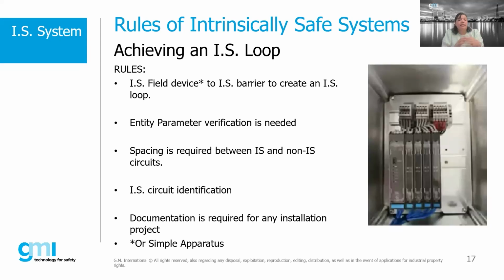So one rule is the first one we just talked about: an intrinsically safe certified field device connected to an intrinsically safe barrier, Zener or galvanic isolator - it needs to be an intrinsically safe barrier to create that loop. There must be an entity parameter verification. That's also very, very important, and we're going to talk a little bit more about that to make sure we're actually creating that IS loop.